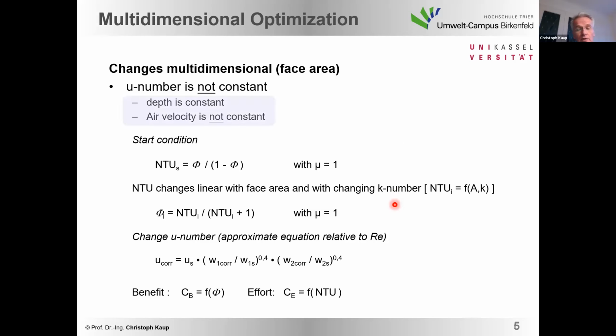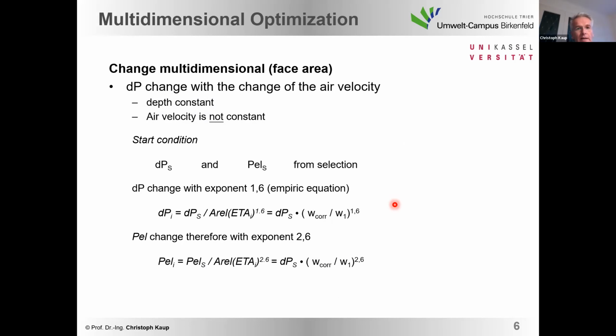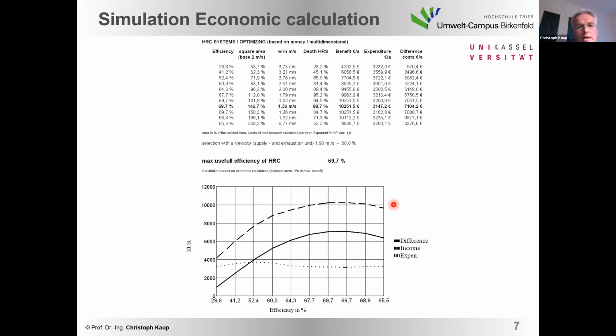And for sure, now air velocity isn't constant, so we need an approximation equation to recalculate the U value, the thermal efficiency of our thermal transmission process. So at the end, we also have to change the pressure loss, and that's the reason why we do that. We would like to have P electric, the electric power consumption, because that is the investment to keep the heat recovery running. It will not be operated without any energy losses. We have to invest electric energy to keep the heat recovery in operation. And now here we see the 3D optimization.